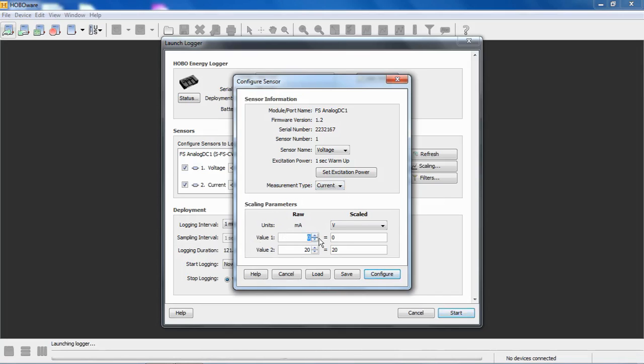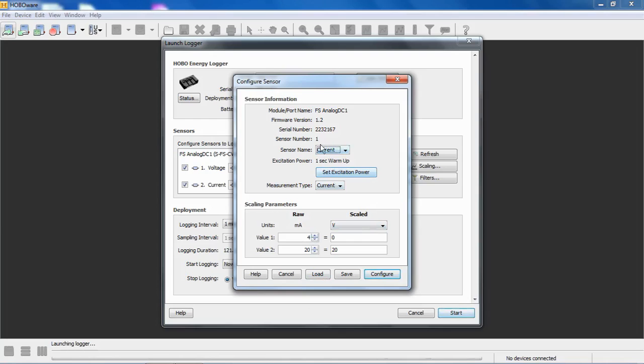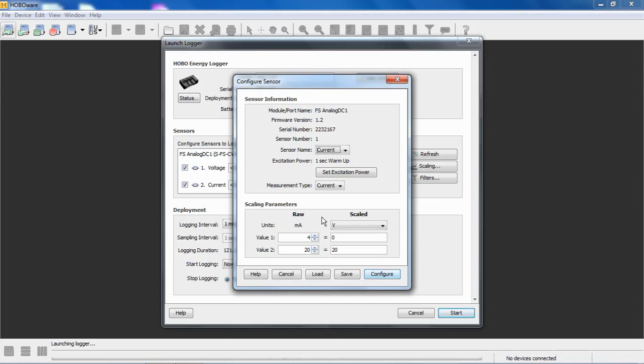Let's say this is a 4 to 20 milliamp output sensor. We'll go back up here and change our sensor name to current. And again, this will be the name of the sensor. And again, you can name it anything you want using the custom configuration. So what we're saying is that the 0% output of this third-party sensor is 4 milliamps, and the output is 20 at 100%. And then we can set up a relationship to how we want this to be displayed in the data set in engineering units. So if it's gauge pressure, if it's differential pressure, if it's some other type of measurement, we can set up that relationship here.